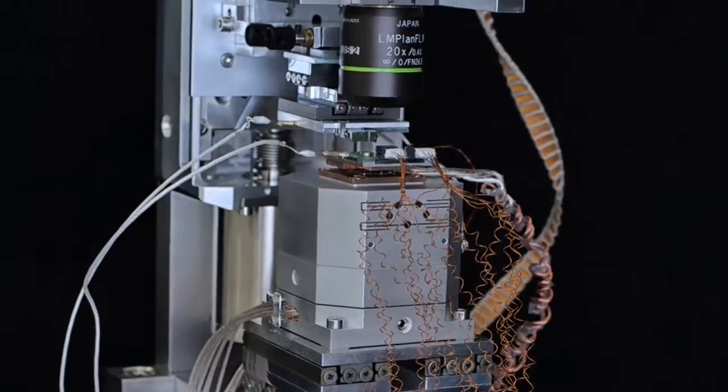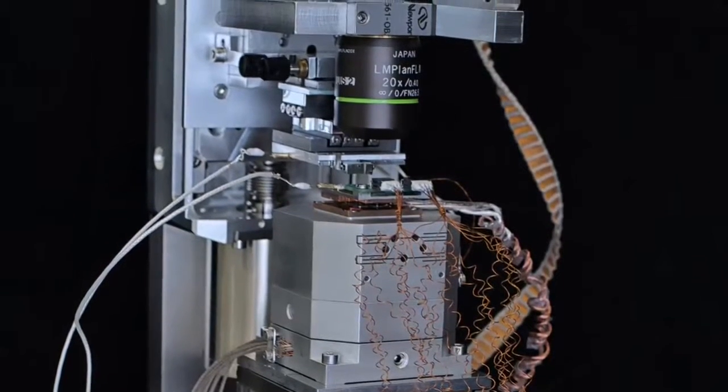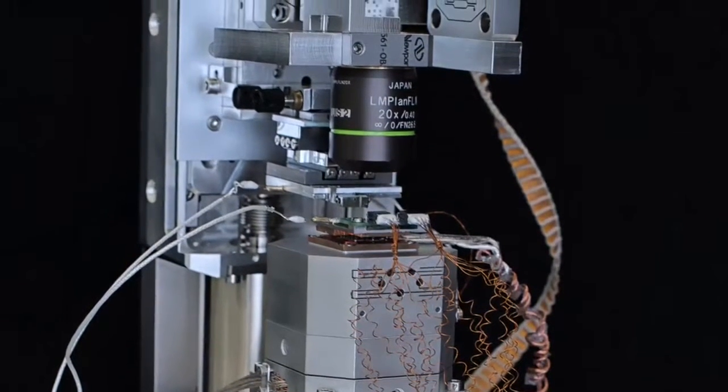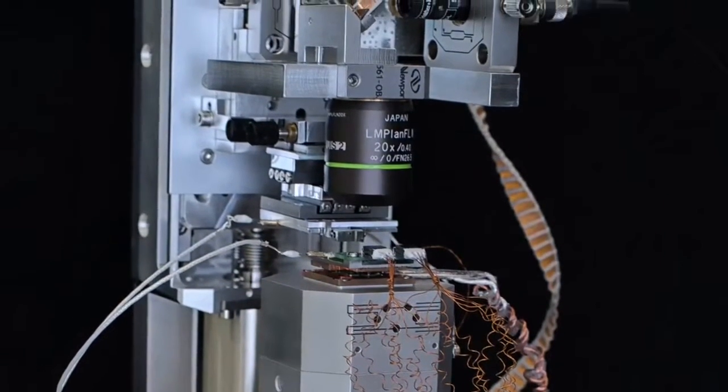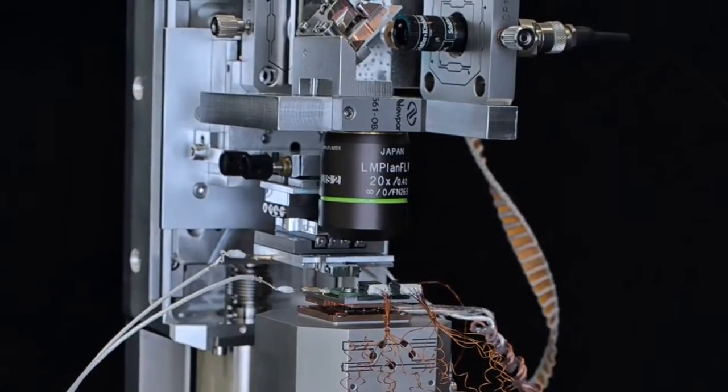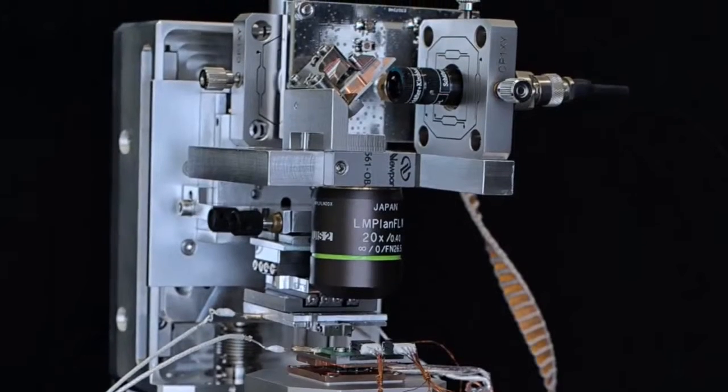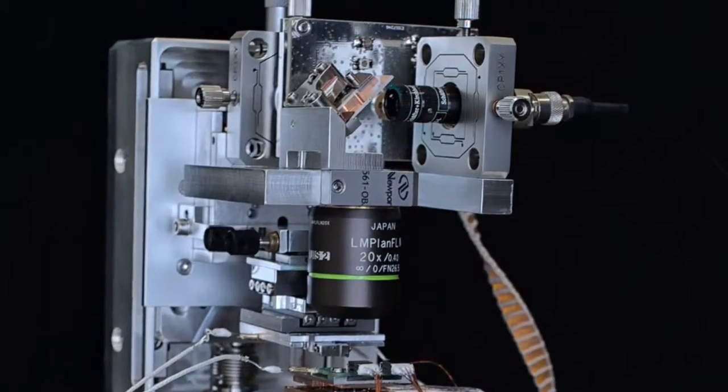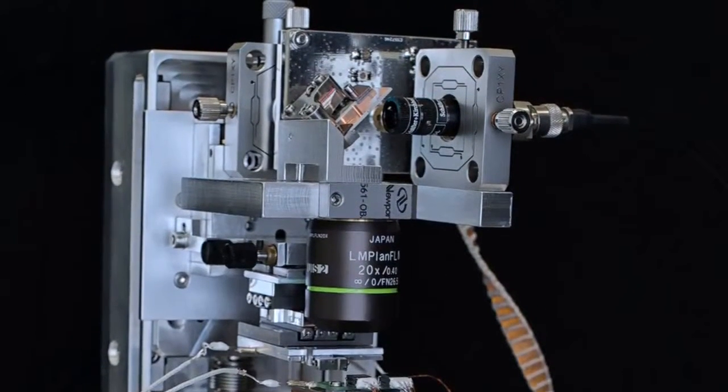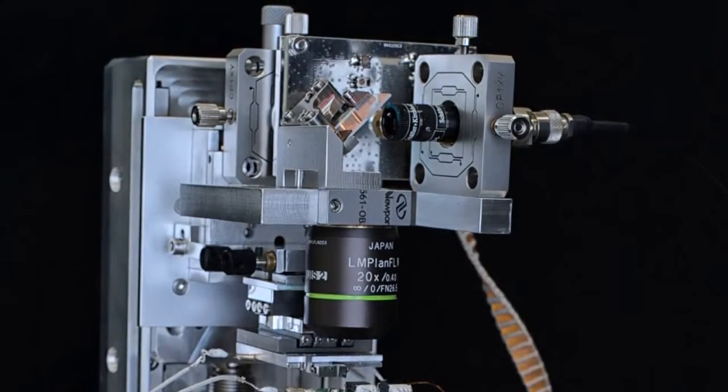Here we have the cantilever holder, where the actually sensing element of our thermal microscope is situated. And on the top part we have an optical beam deflection system, as you may find it also in a regular AFM, to detect the motion of the cantilever, which gives us information about the surface topography.